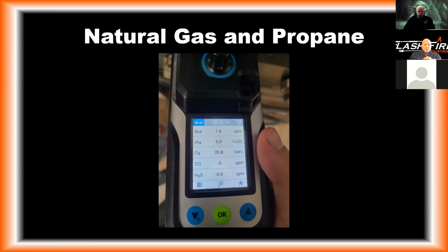So while it's not a true leak detector, you are getting readings of that natural gas or propane at a lower level, because you're reading the ethyl mercaptan in a parts per million range versus a percent LEL range. And remember what we said, 1% is 10,000 parts per million, depending on how the meter's calibrated. So it's a tremendous amount of gas in order to get that LEL sensor to move.